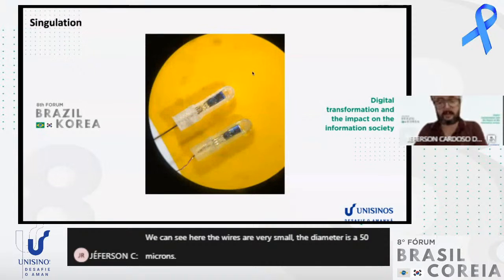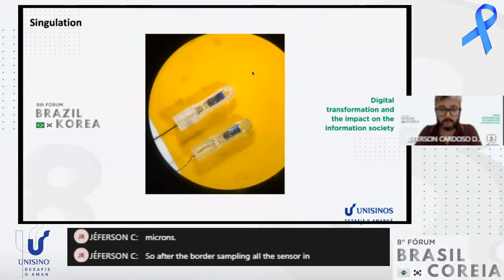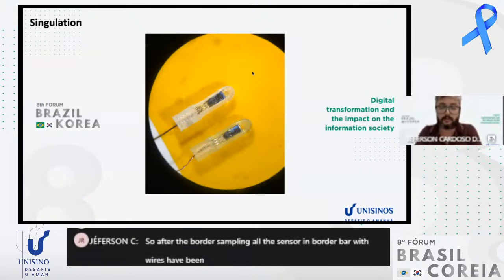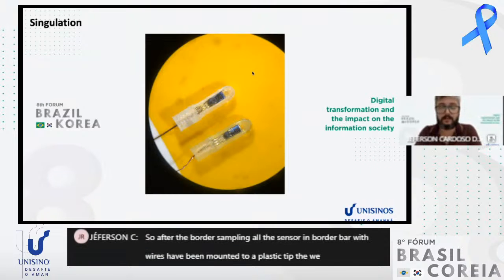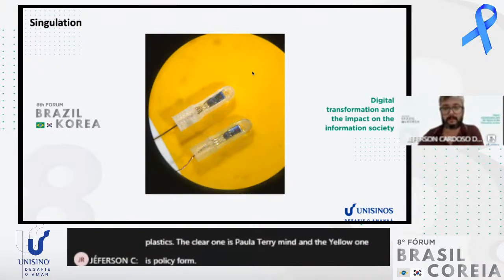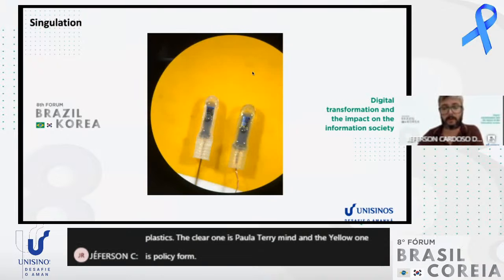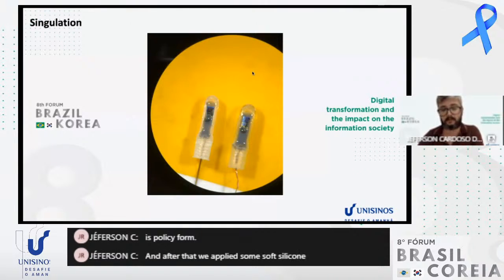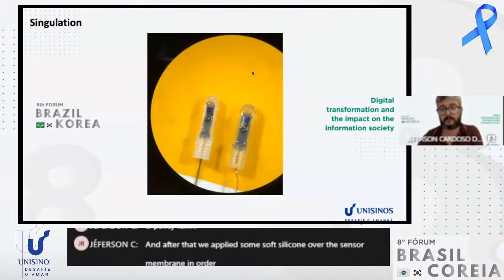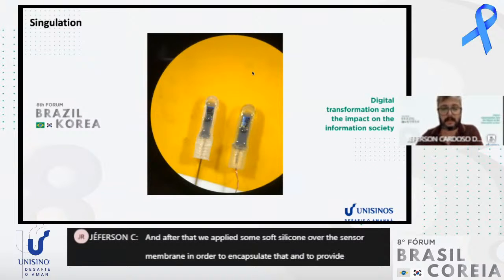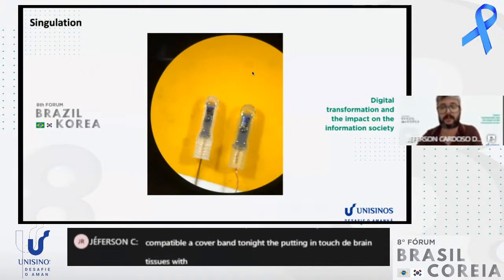After the board assembling, the sensor and board with wires were mounted to a plastic tip. We tried different materials, but all biocompatible plastics. The clear one is polyetherimide, and the yellow one is polysulfone. After that, we applied some soft silicone over the sensor membrane to encapsulate it and provide a biocompatible cover, so the brain tissues don't come in contact with the electronics inside.